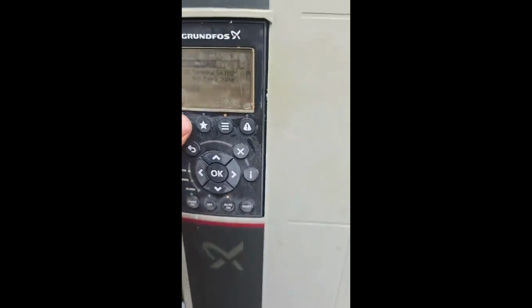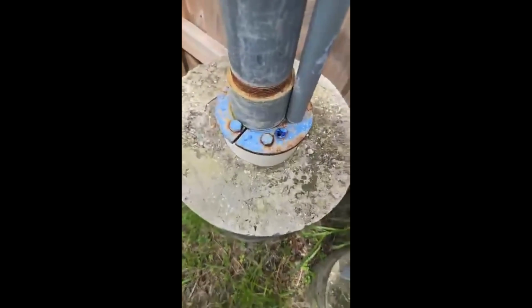So this drive got put in, installer came back, put an aftermarket transducer on it when the transducer failed. And then they didn't rescale the drive to the aftermarket transducer. So what we got into was, number one, this thing was running continuous, never shutting off. But you take a look here, PVC casing. That's a recipe to melt this pump to the casing. So it thought it was trying to get 60 psi. It was over here running at 79 psi and not going to sleep, because the sleep settings had not been adjusted at all in this drive.